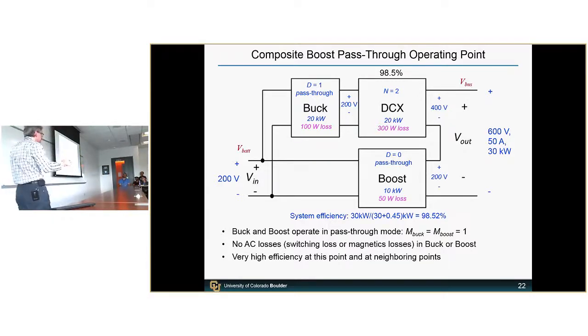The important point is that when we go outside of the pass-through mode, our efficiency remains high because, again, we're not torturing the components involved in regulation. We're exposing them to small levels of indirect power processing and achieving regulation with minimum additional loss on those modules.